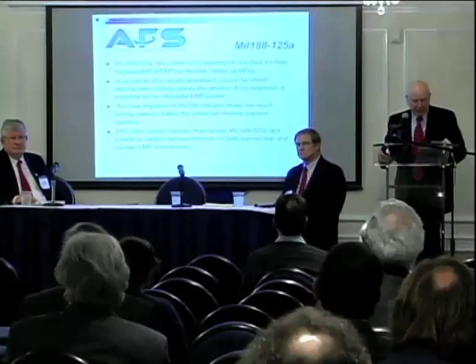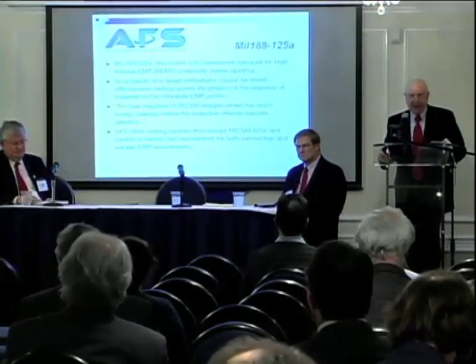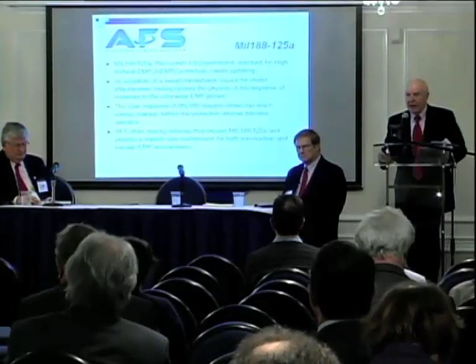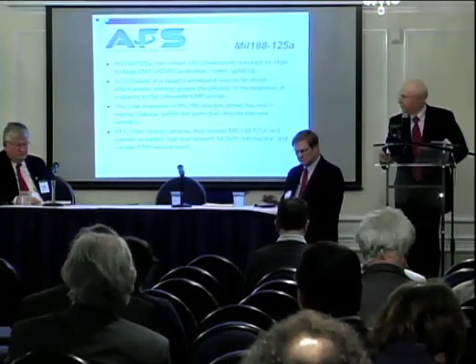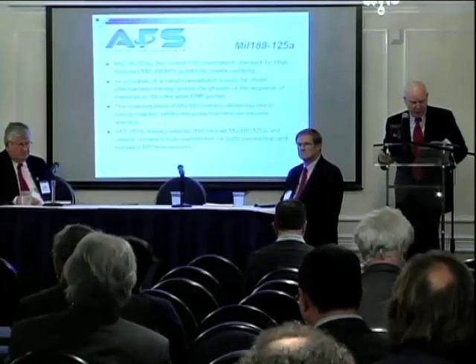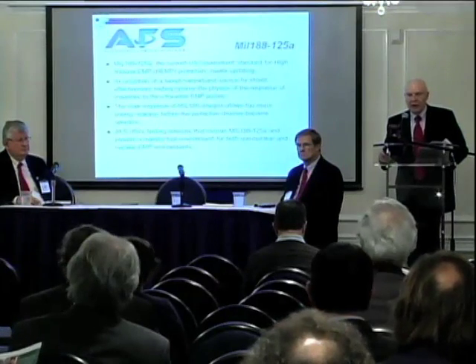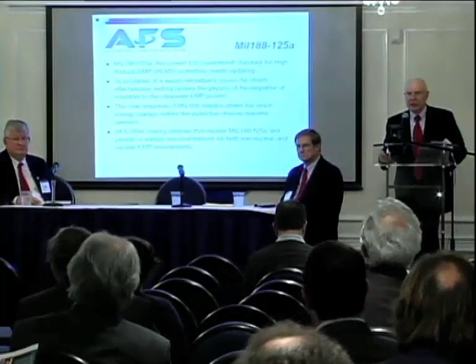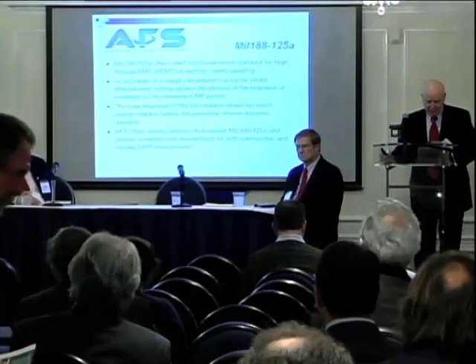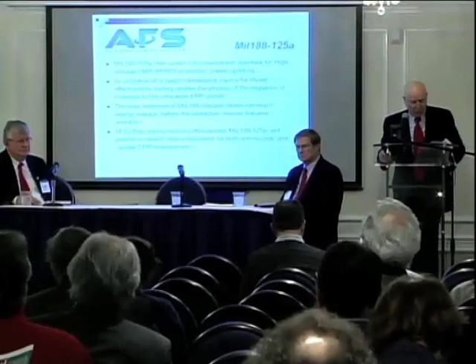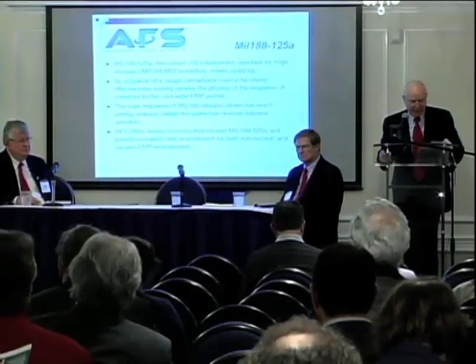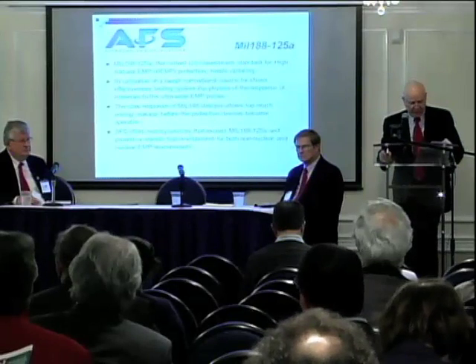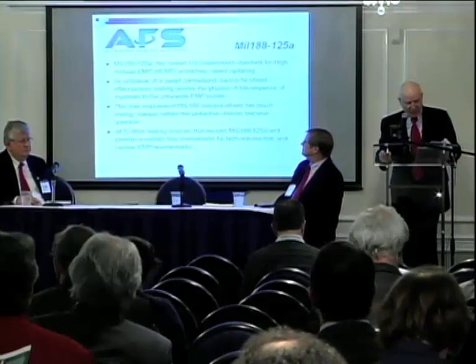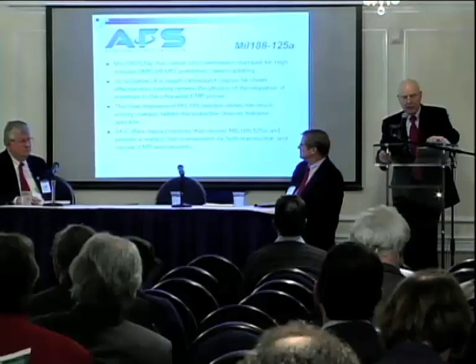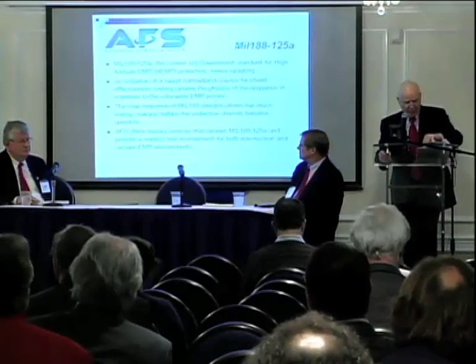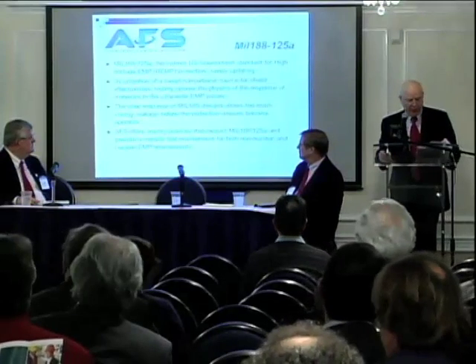MIL 188 is the current government standard for high altitude EMP protection. It was good at the time, but it needs updating. The utilization of a swept narrowband source for shield effectiveness ignores the physics of the response of materials to an ultra-wide EMP pulse. The slow response of MIL 188 designs allows too much energy leakage before the protective device becomes capable. AFS offers some testing services that exceed MIL 188 and gives us a realistic test environment for nuclear and non-nuclear environments.